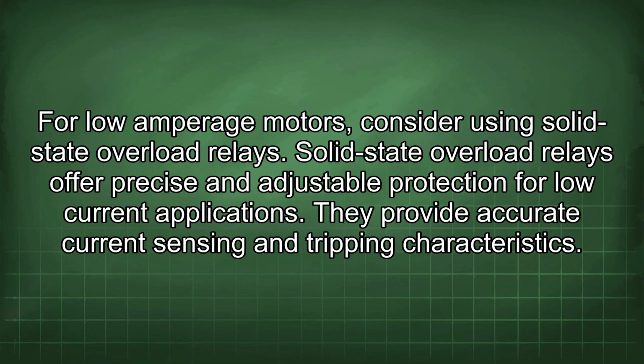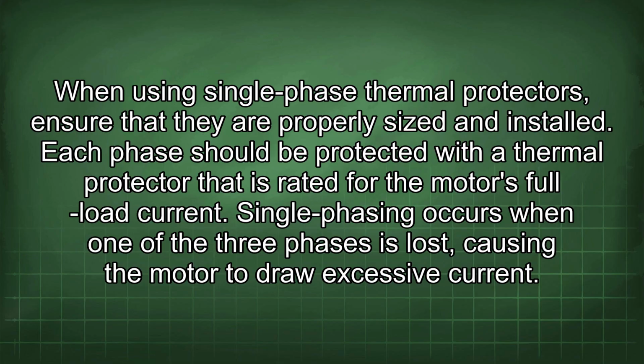For low amperage motors, consider using solid-state overload relays. Solid-state overload relays offer precise and adjustable protection for low current applications. They provide accurate current sensing and tripping characteristics. When using single-phase thermal protectors, ensure that they are properly sized and installed. Each phase should be protected with a thermal protector that is rated for the motor's full load current.